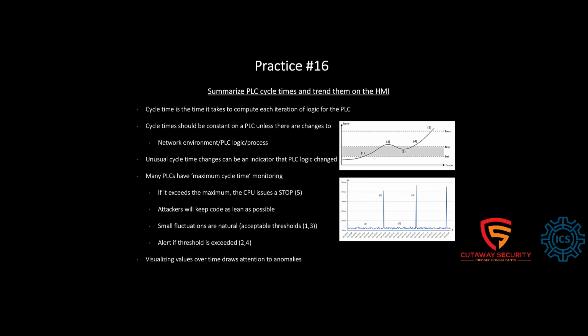Those things are usually available in the PLC, but they're diagnostics only. So you probably have to connect the EWS or a laptop to be able to look at these things. But most PLCs will allow you to write these to a register. And then, of course, you can trend them, historize them, connect them to your historian, send data over to the HMI for the trends. But you have to do it manually, or you have to do it on purpose, because historically this was not done.